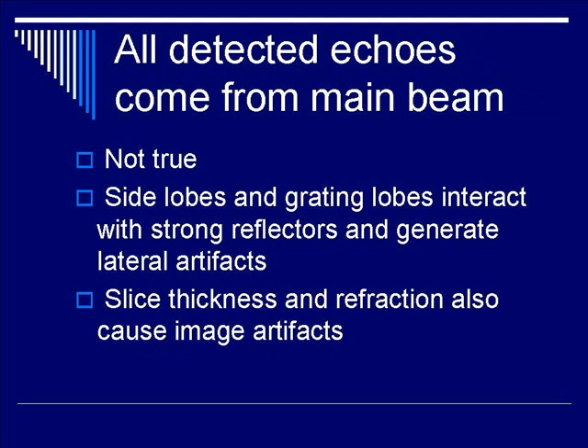Finally, the assumption that all detected echoes come from the main ultrasound beam is sometimes erroneous. Even in today's array ultrasound probes, you will still see side lobes and grating lobes interacting with strong reflectors within the body, generating lateral artifacts. In other words, the main part of the image will be cluttered with artifacts from adjacent structures that sometimes are not even from the plane of interest. Specifically, slice thickness and refraction can cause many of these image artifacts.